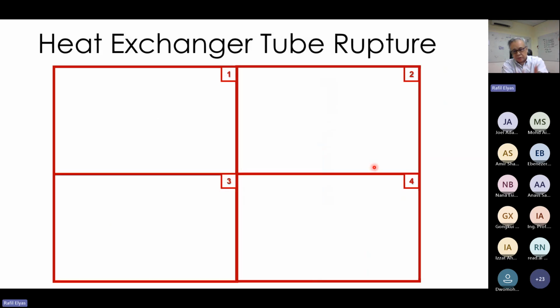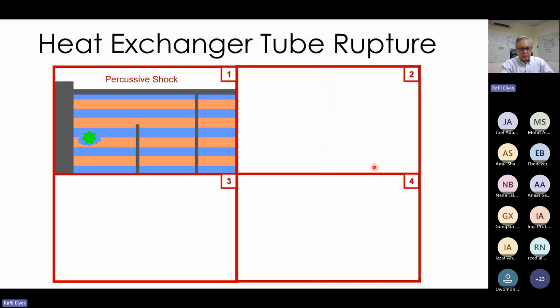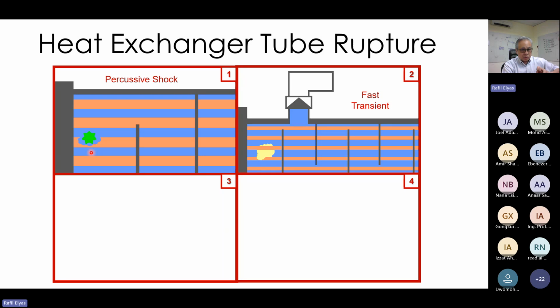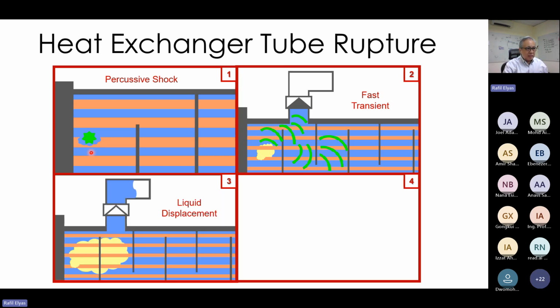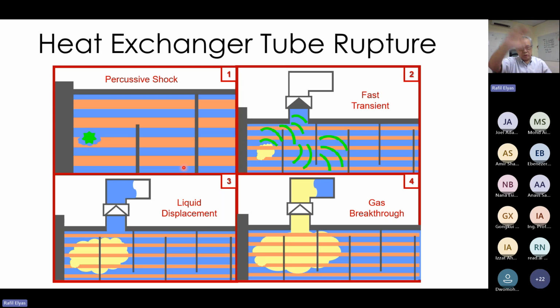Okay, so if we take a look at the dynamics of a tube rupture, the first thing that happens when you have a rupture is a percussive shock. As soon as it breaks, you've got high pressure suddenly entering a low pressure system. That percussive shock is extremely fast. You have a pressure wave that travels at the speed of sound in whatever liquid you have. That high pressure is followed by a liquid displacement and later by gas breakthrough. So when you're designing these relief systems, you need to take all of this into account.